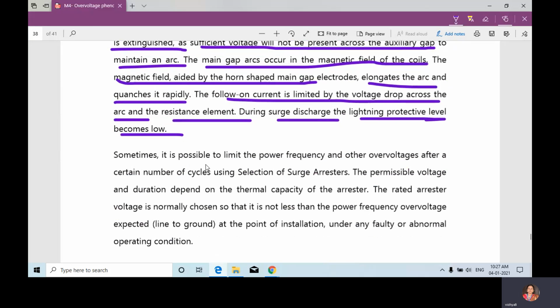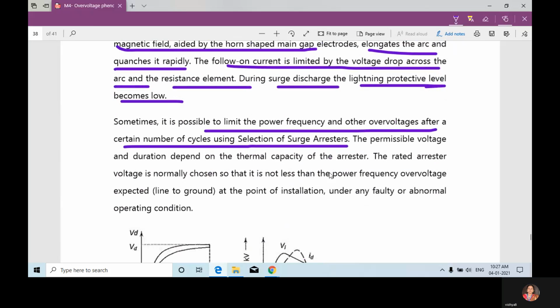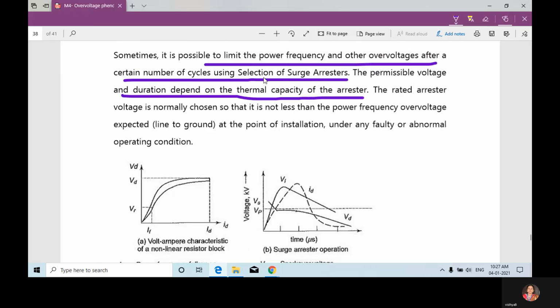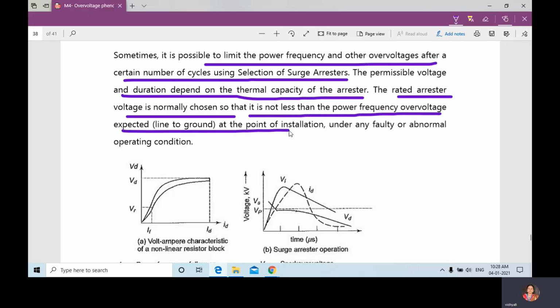Sometimes it is possible to limit the power frequency and other overvoltages after a certain number of cycles using a selection of surge arrestor. The permissible voltage and duration depend on the thermal capacity of the arrestor. After a few minutes or a few seconds, we can limit the power frequency and other overvoltages by using what? By using selection of surge arrestor. The rated arrestor voltage is normally chosen so that it is not less than the power frequency overvoltage expected at the point of installation under any fault or abnormal operating condition.